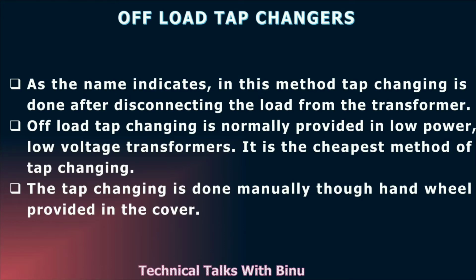Off-load tap changer is a method of changing the taps once after disconnecting the load from the transformer. Off-load tap changers are normally provided for low power, low voltage systems and it is the cheapest method of tap changing. Tap changing will be done manually through a hand wheel which is provided at the cover of the transformer.